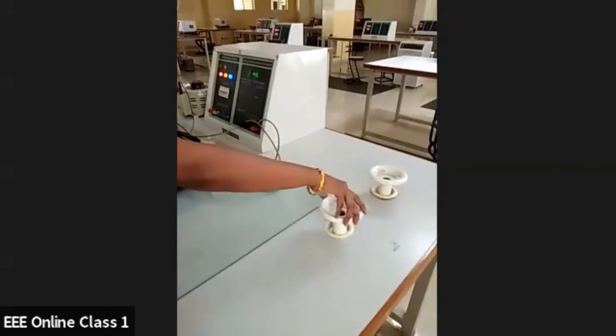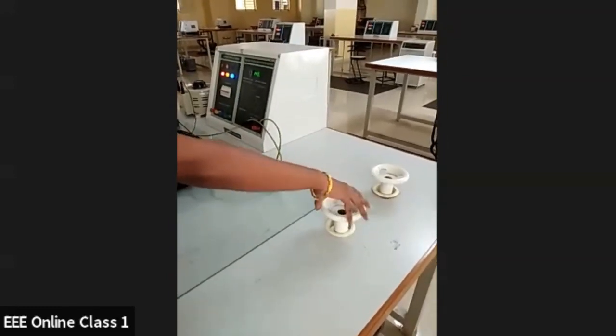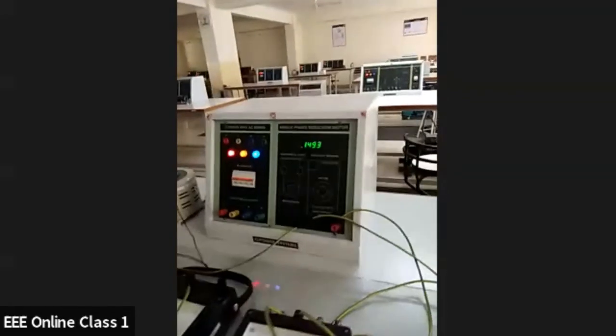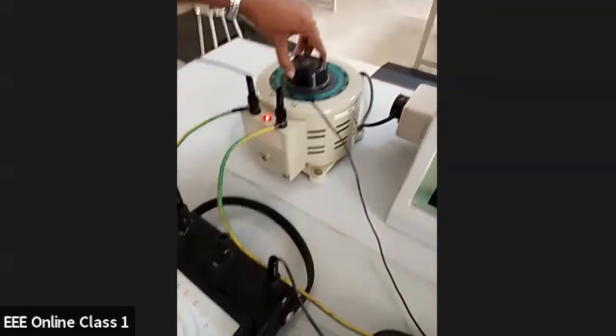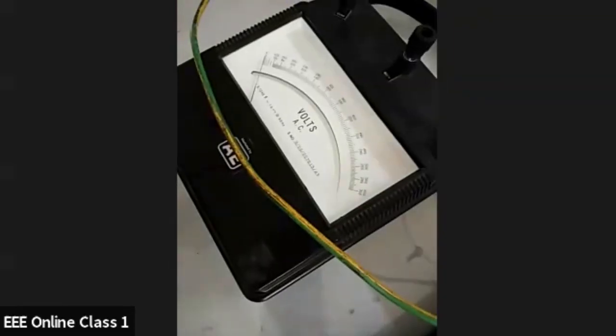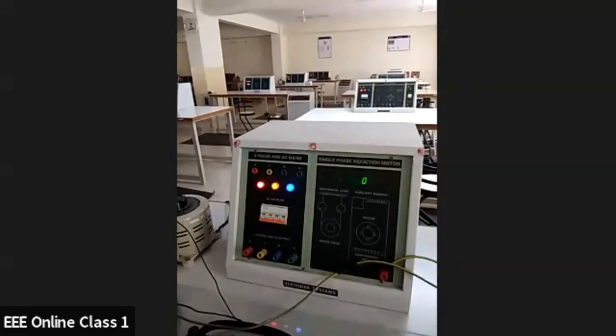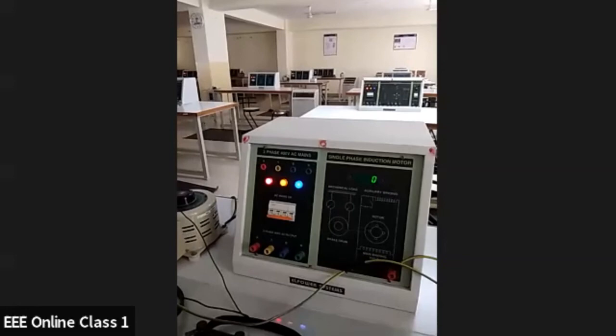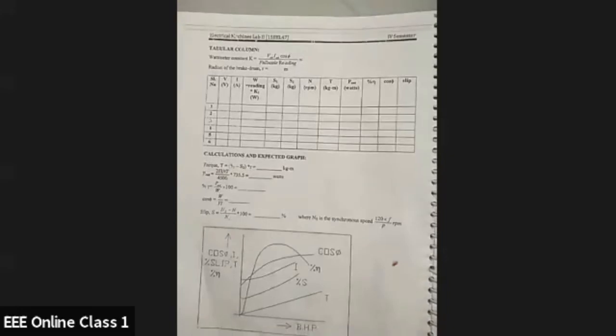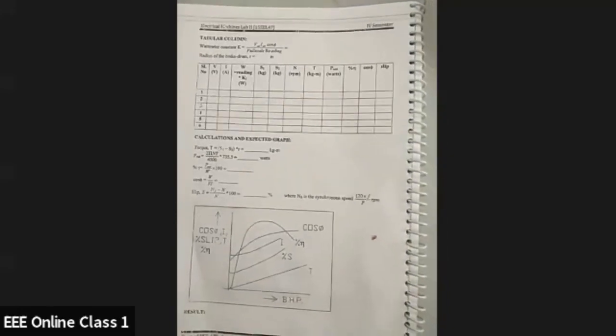So we have to go back to that initial condition where the loading was totally zero. Once it is brought back to the no load condition again, the voltage has to be reduced back to zero. In the auto transformer, we have to bring the voltage back to zero. Once the voltage is zero, reading zero across the voltmeter, switch off the supply. So we would have noted down voltage, current, wattmeter, S1, S2 and speed.